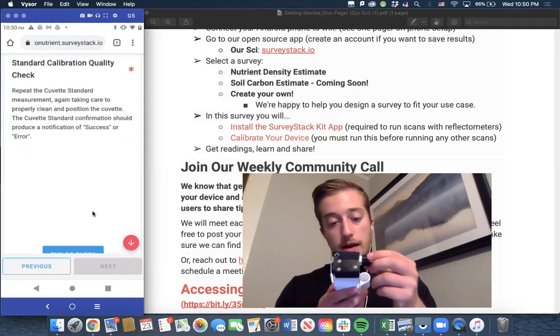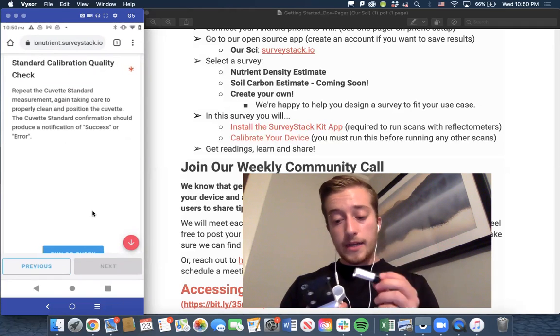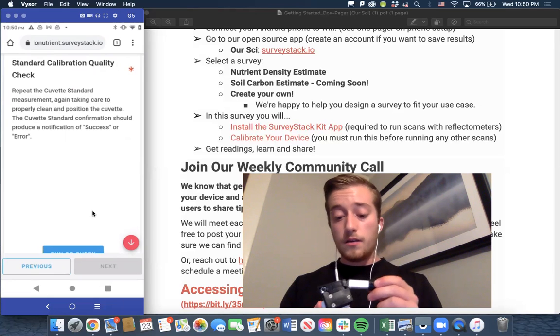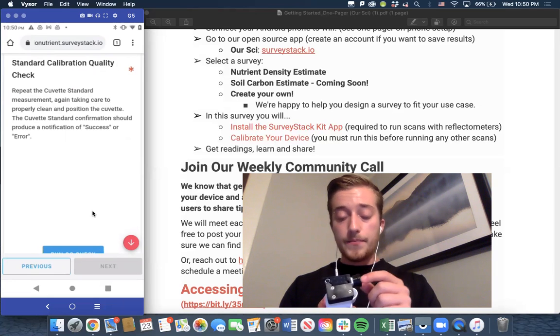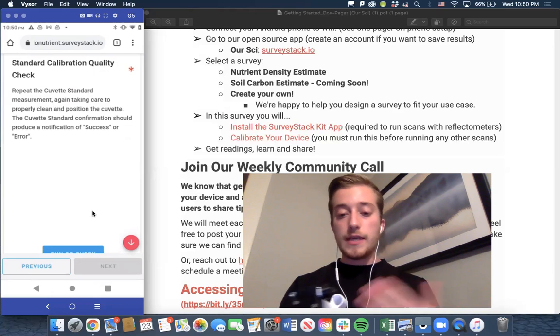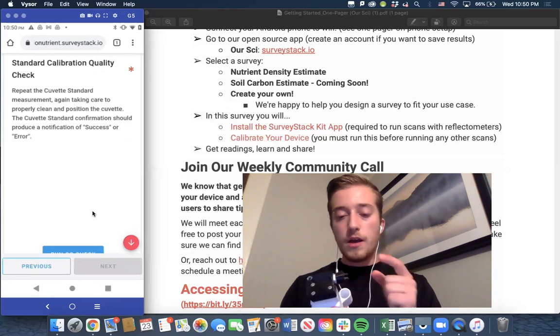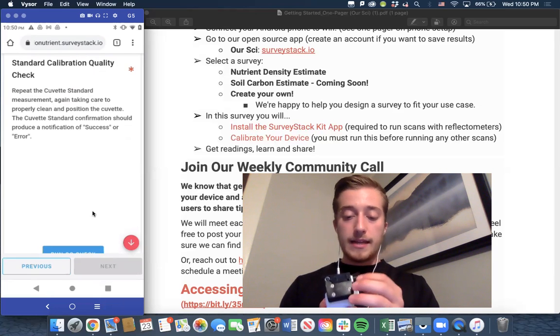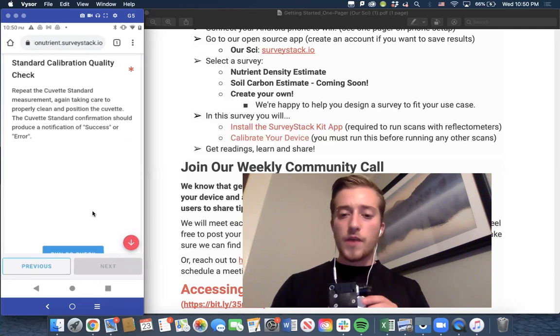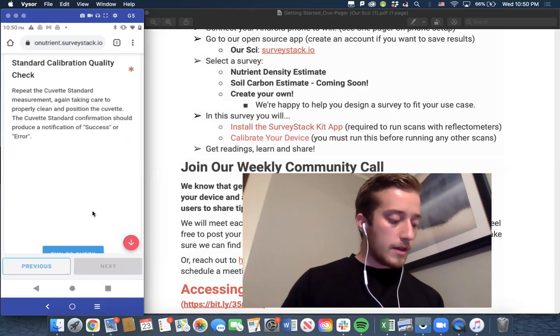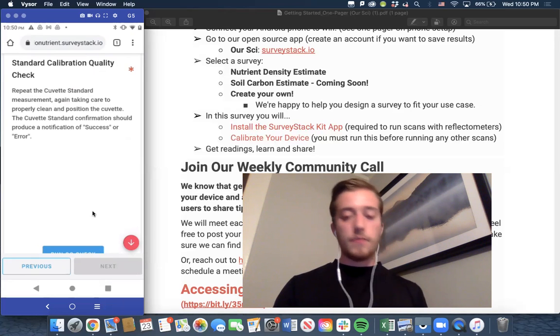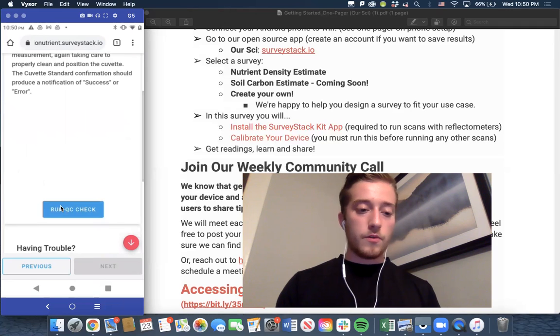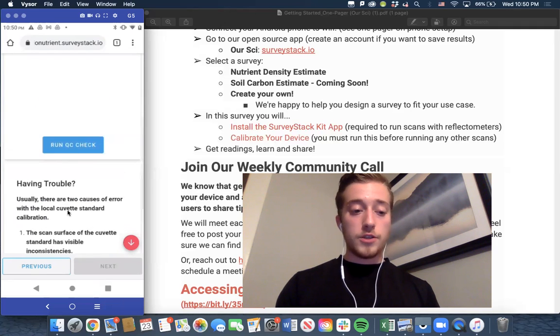So for this, I'm going to remove my cuvette standard and I'm going to reinsert it. I want to make sure I'm getting, if I leave it in and just rescan, that's essentially the same data point as before. I want to make sure I'm getting a new data point, but that it is calibrated correctly so that my device recognizes this as similar to the calibration. So remove it, reinsert, make sure it's aligned properly as before, and we'll run our quality check.